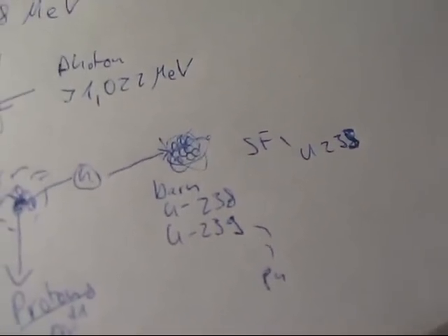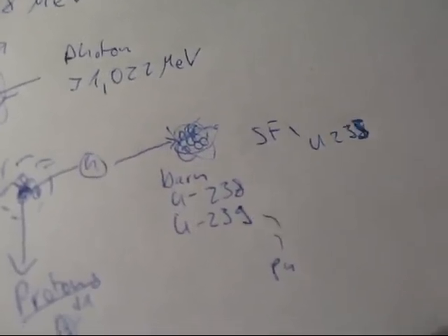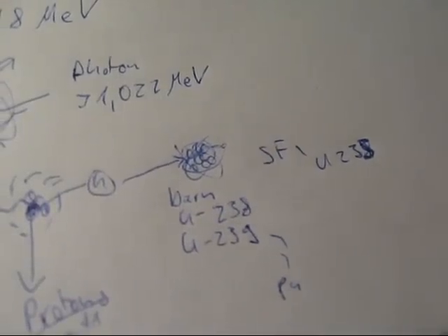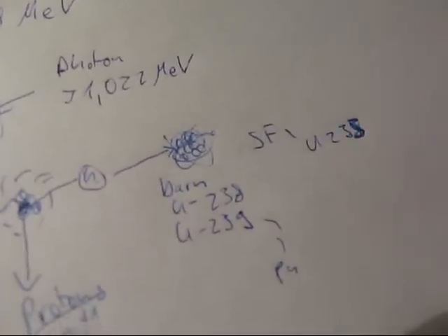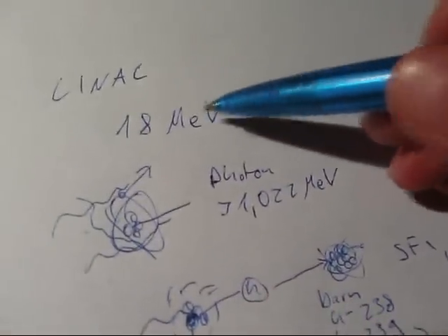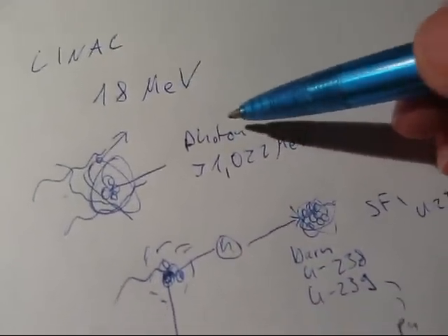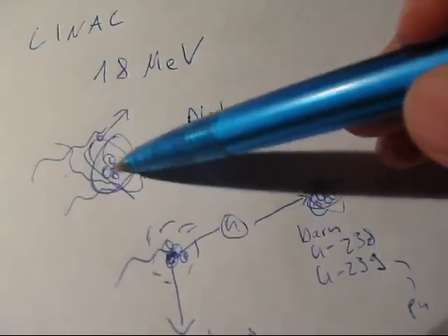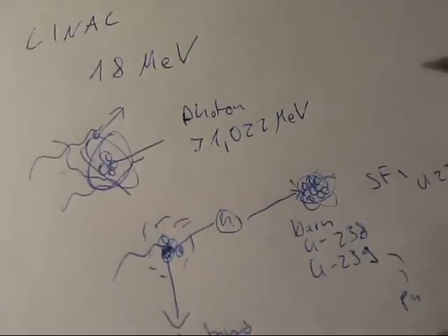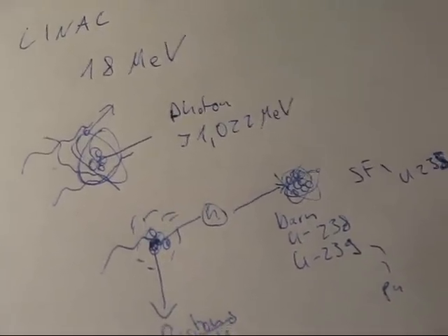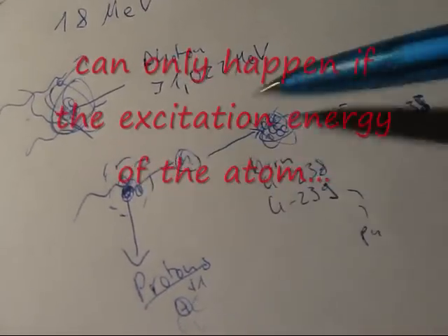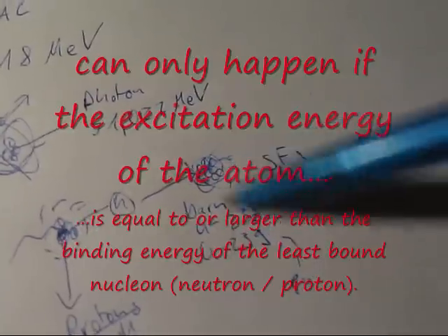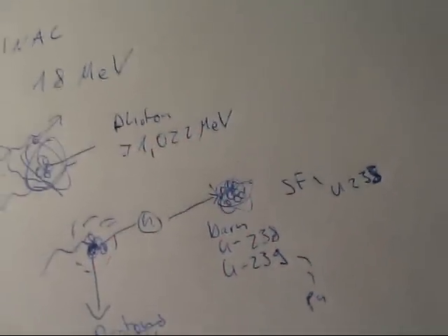Or, well, as I said, they might just turn into radioactive elements, like uranium. But not only uranium does this, a lot of elements do, with varying probabilities. So, it really depends. So, as I said, we had an 18 mega electron volts photon beam that exceeds this critical energy, where the photon might get into the core of an atom or whatever is present in the beam or near the photon beam. And that may result in protons and neutrons being ejected, which, again, might be captured by other atoms, and these might turn radioactive.